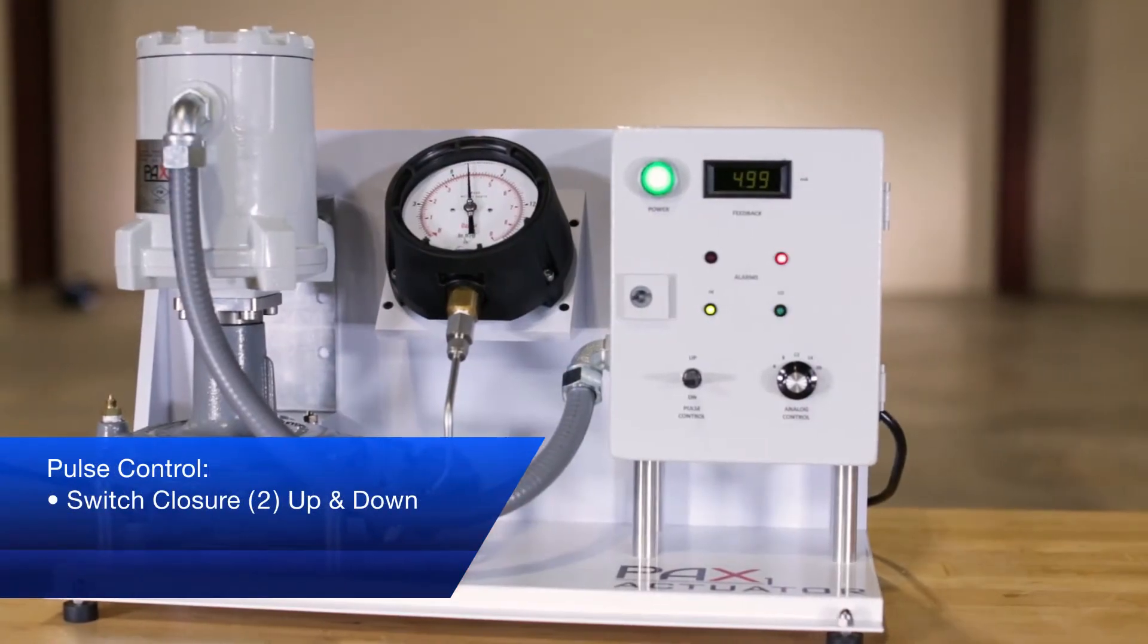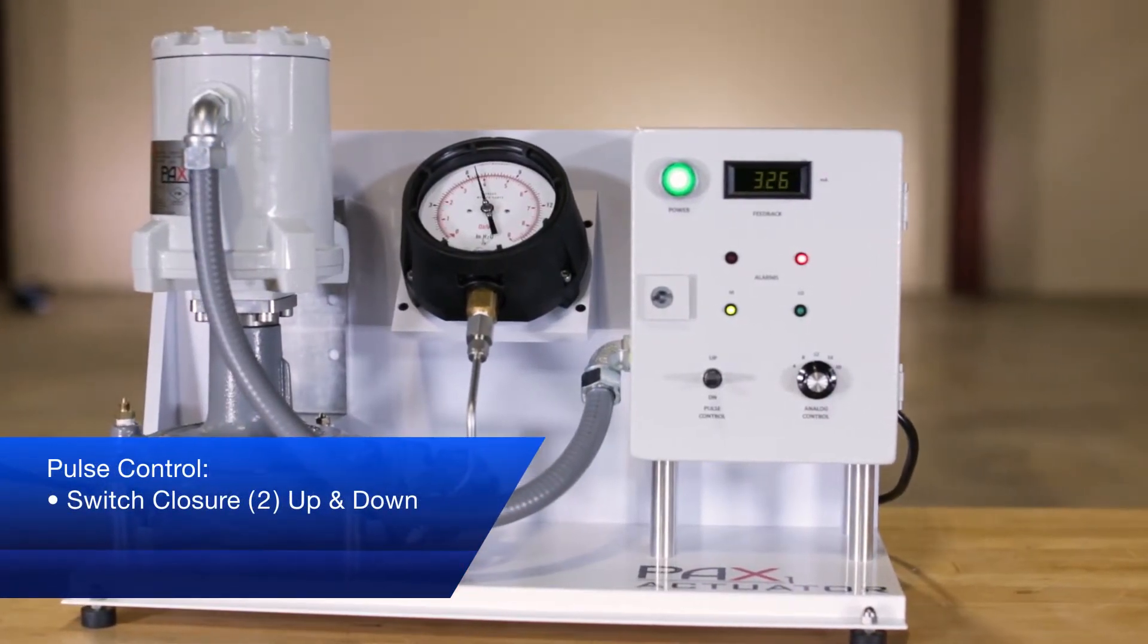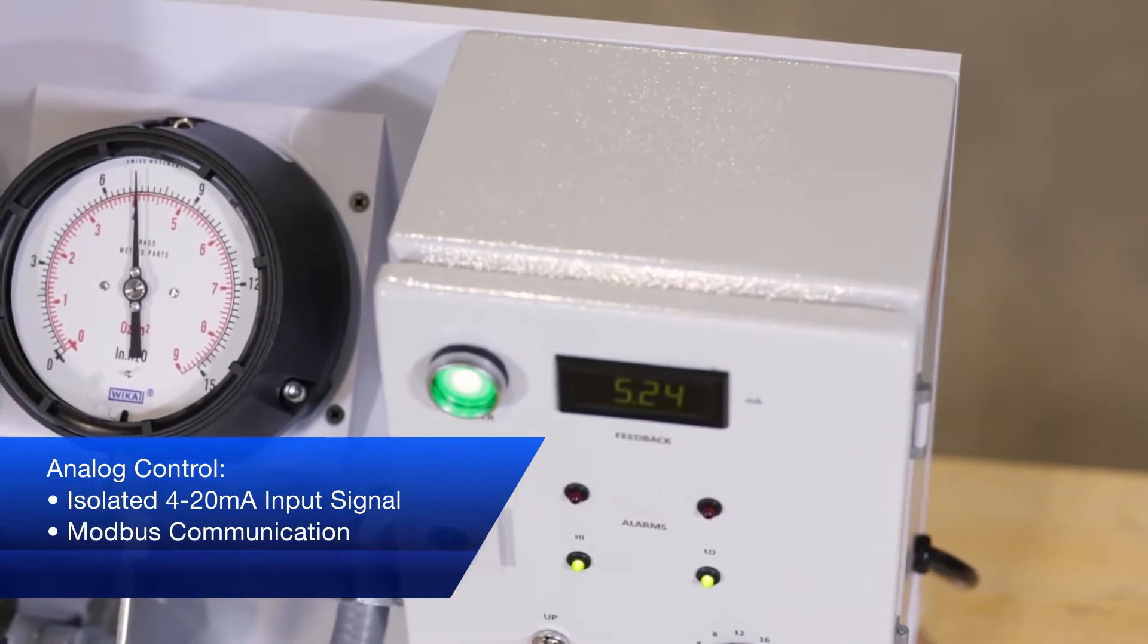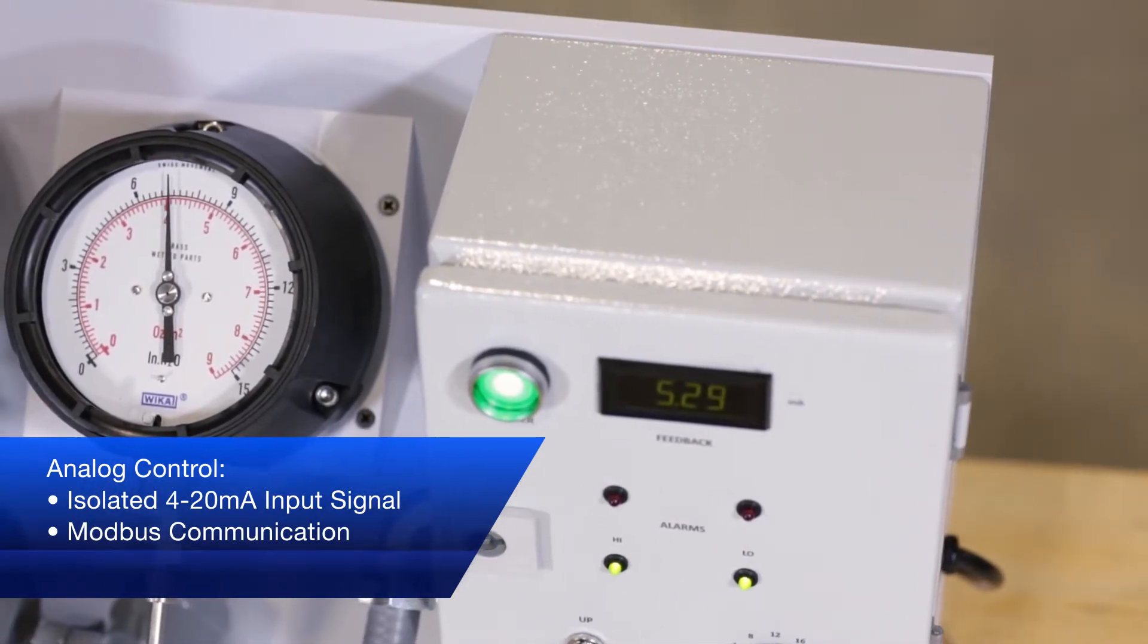The PAX 1 can be configured for pulse or analog control. Analog control can be from either an isolated 4 to 20 milliamp input or Modbus communication.